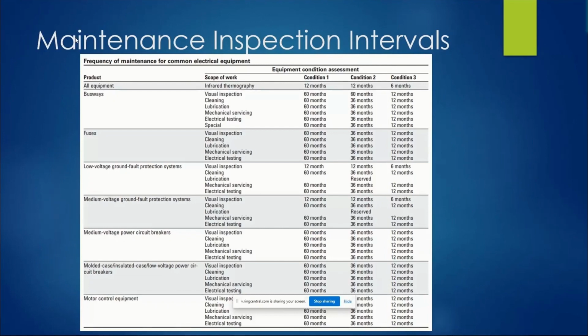There's been a practice within the industry over the past 30, 40 years that I've been doing this, of just doing your switchgear and panel board testing every 10 years, and that's all fine. But the standards have changed and updated. Now it is every 5 years or 60 months, that's the longest interval you're going to find. There's going to be a cost factor that goes into this, but this is something we have to budget in and put in place. These new standards are pretty stringent on the intervals, a lot tighter than what we've been used to.